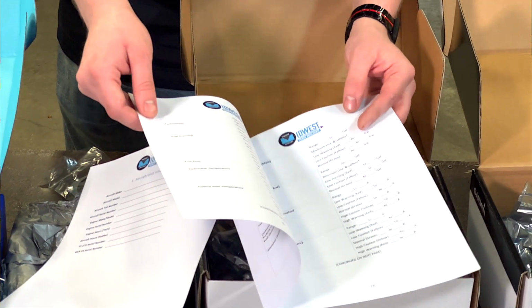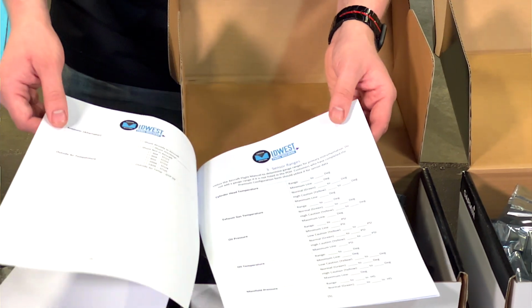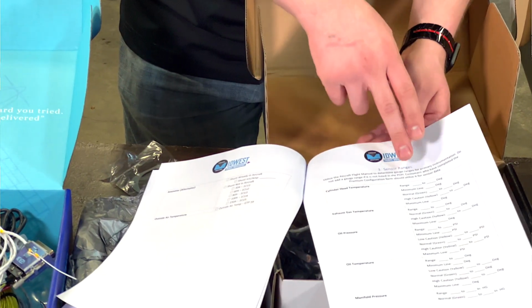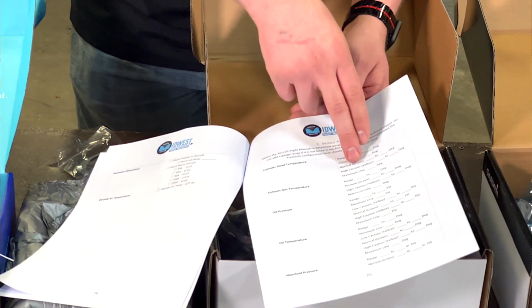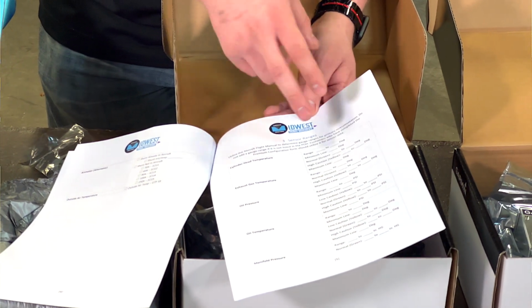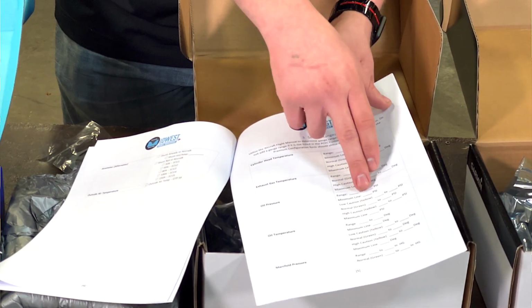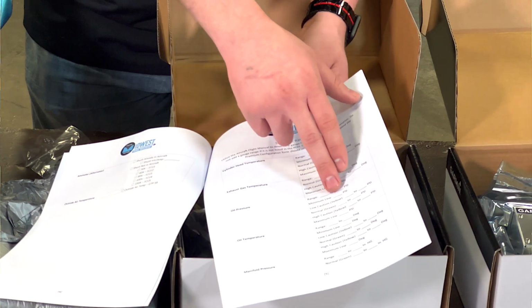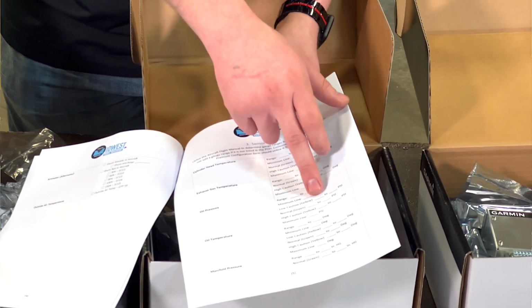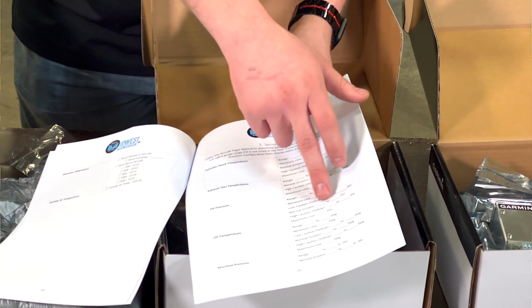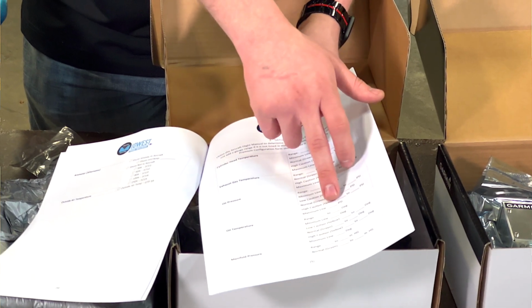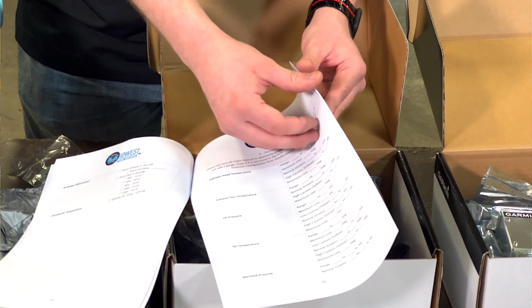As we move on through the pages, you can see this is where we actually put in our gauge ranges. For example, oil pressure - maybe your minimum red line is 24 psi, so you write that in. If you have a yellow range, write it in, a green range, a high yellow range, and a maximum line. You put all that information in here.